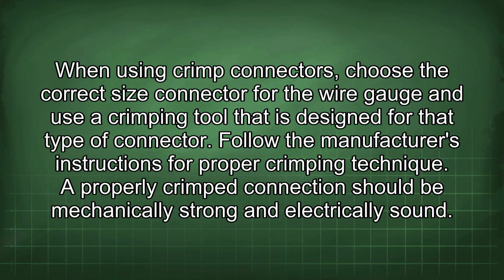When using crimp connectors, choose the correct size connector for the wire gauge and use a crimping tool that is designed for that type of connector. Follow the manufacturer's instructions for proper crimping technique. A properly crimped connection should be mechanically strong and electrically sound.